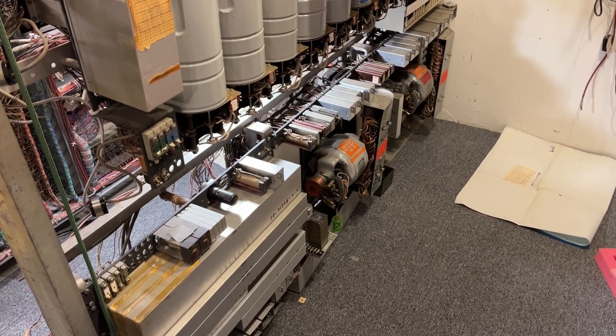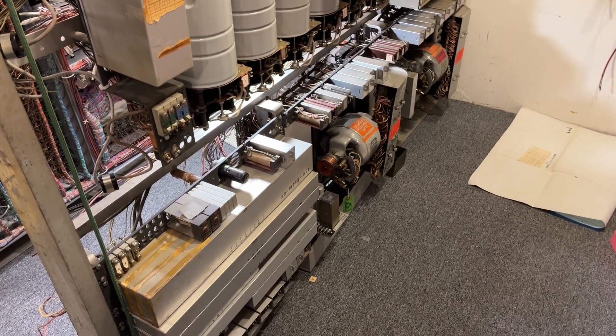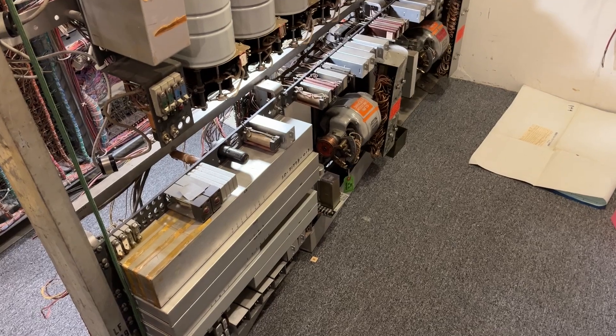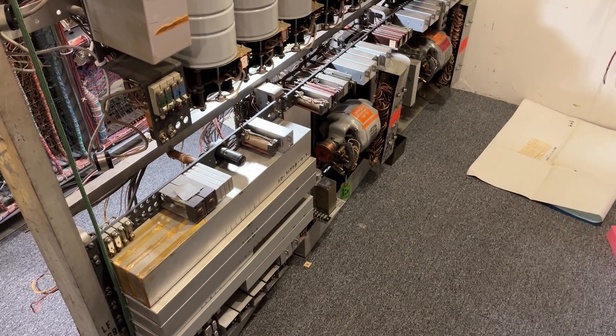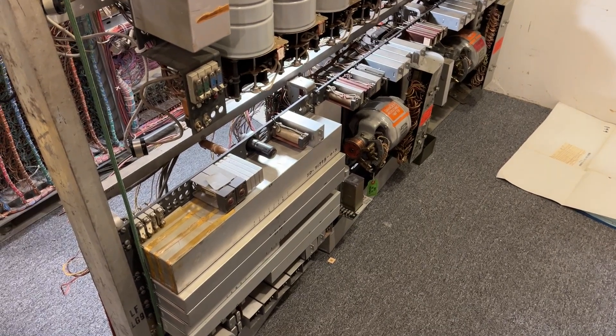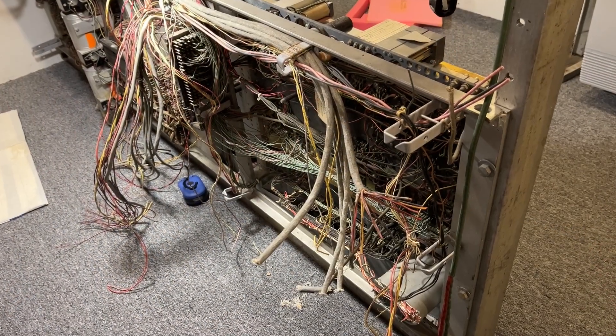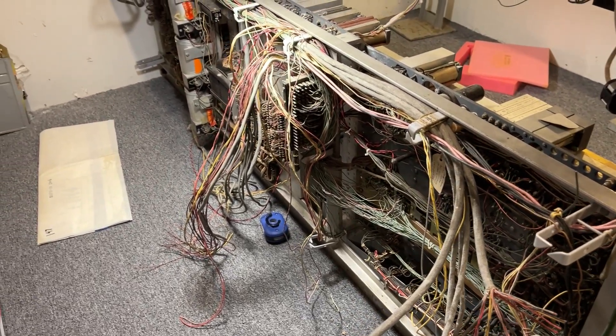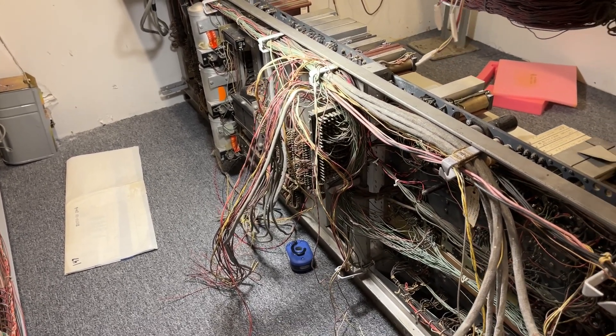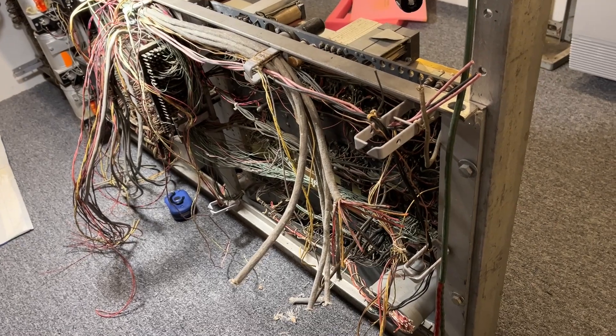Today's presentation will be me working on a Western Electric 1939 with extreme, serious modifications over its lifetime — ringing and tone plant. There are two motor generators, G1 and G2, and over on the left side of the screen is the alarm sender, and some control relays, in addition to the relays atop of the generators that do control and alarming. All of the wires that you see, the spaghetti mess, are the wires that went to the switching equipment and power at one time. About 80% of these wires will not be used in this application.